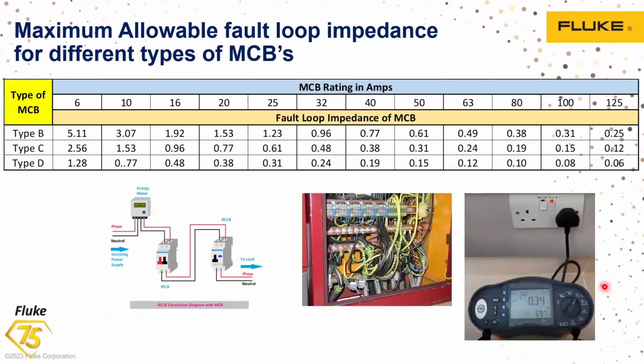Now, what are the maximum allowable ratings for different MCBs? Because there are type B, type C, and type D. So assume that if I take a 6 ampere MCB, the fault loop impedance of that MCB is 5.1 for type B, and 2.56 if it is type C, and if it is type D, it is 1.2.